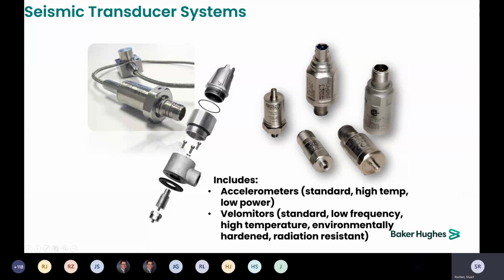We do offer a protective housing. So once the sensor is mounted to the machine, you can have the 3 holes drilled and tapped around it and place this housing over it. There is a gasket to keep out oil, debris, other things, and it gives you protection from environment and from damage from people and other objects. We also offer a spacer. So if you have a taller sensor or a tall connector on there, you can insert a spacer to get clearance for that.